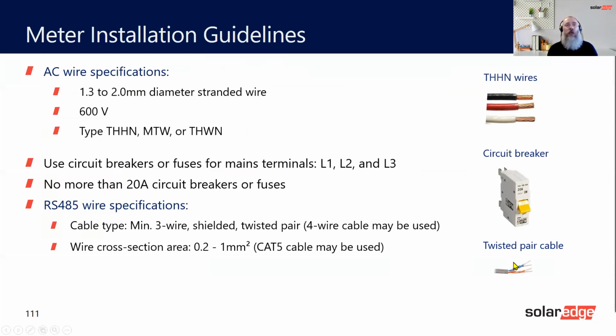Here is your twisted pair. You can see that the blue and white with blue is a pair. The orange and white with orange is another pair. So that's a pair. You only need 2 cables: 2 cables for the B and the A, and 1 cable on its own for the G.